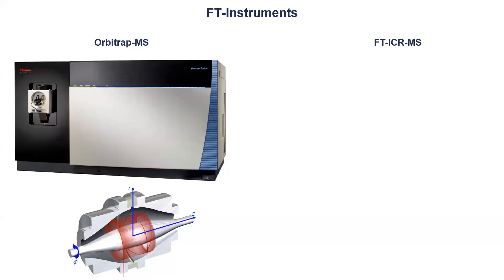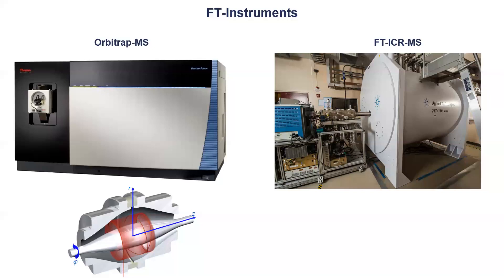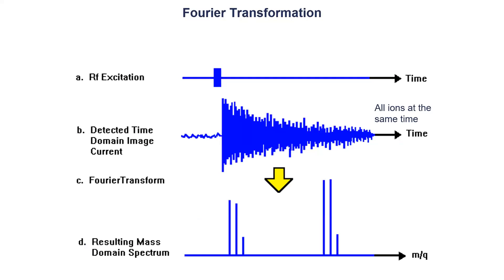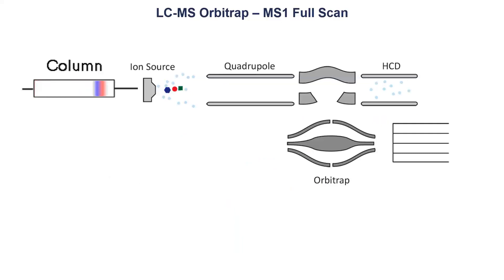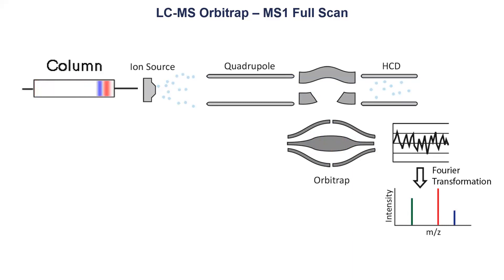If we go to the Fourier transform instruments, we have the Orbitrap on one side and FTICR on the other. These are very specific types of instruments. We actually detect all ions at the same time based on their image current signals. In the Orbitrap, ions oscillate in a specific direction around a central electrode, and this oscillation induces an image current. Based on a Fourier transform computation by the computer, we then get the mass spectrum output. So there is a lot of computation happening behind what you see as raw data. Here is the full setup: the column, ions entering the C-trap, then going into the Orbitrap where they spin and oscillate. The oscillation from left to right gives us the image current, and from that we get our mass spectrum.